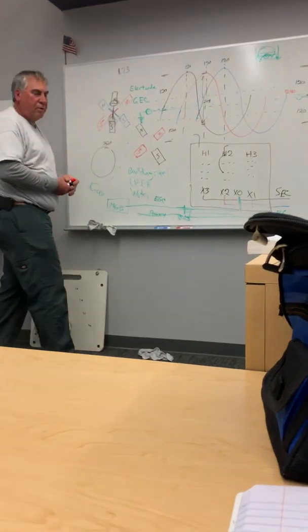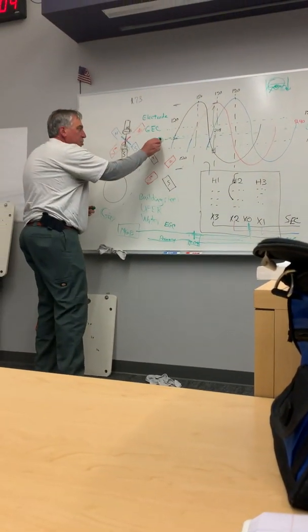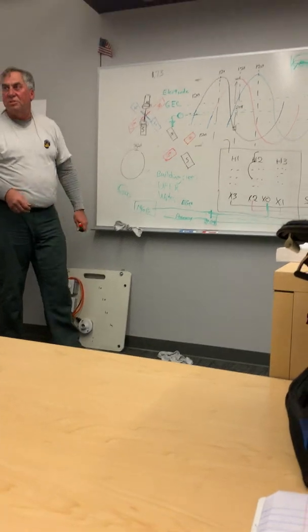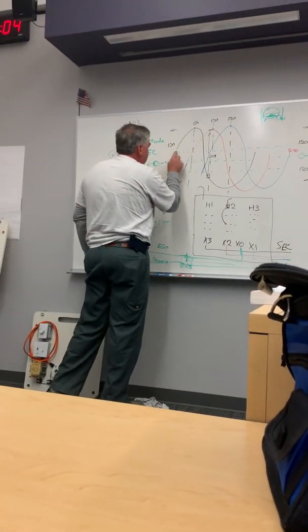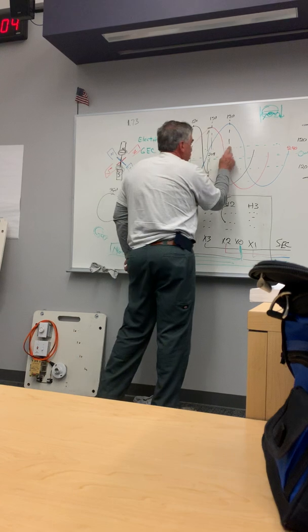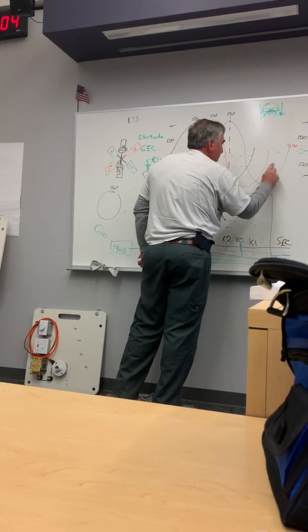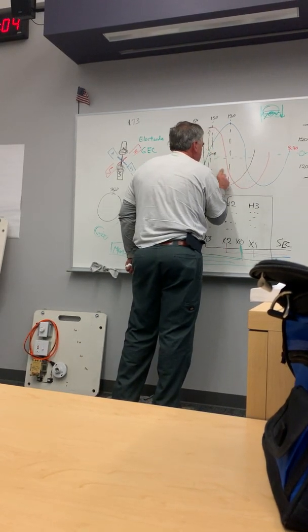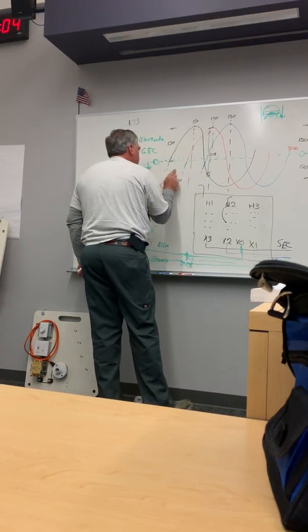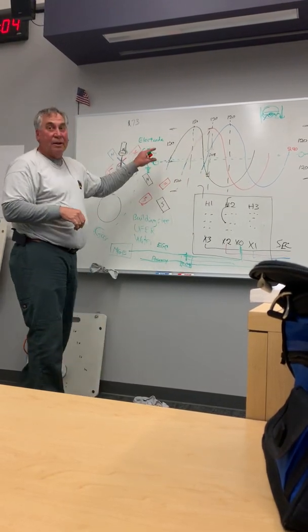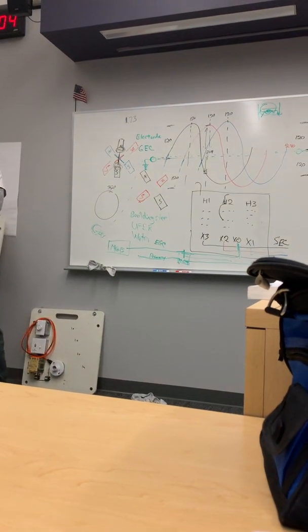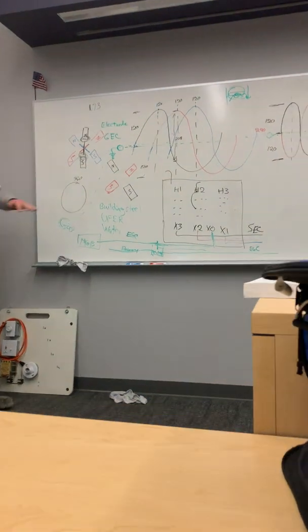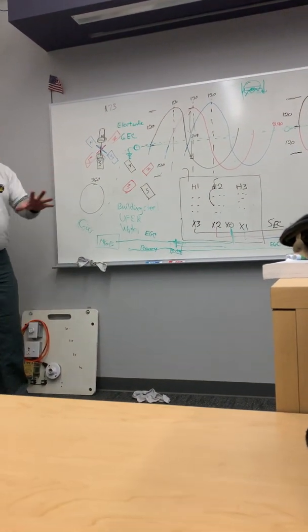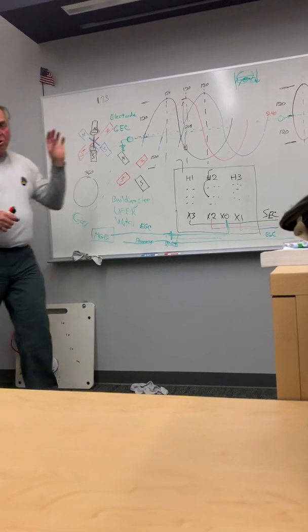I just use that as an example of how critical it is that we keep this zero reference as part of your grounding electrode conductor system for transformers or any separately derived system you create. Now, if we have something being delivered that we've built as a service, and we've established everything and it's good, you can go on and feed the rest of the world.